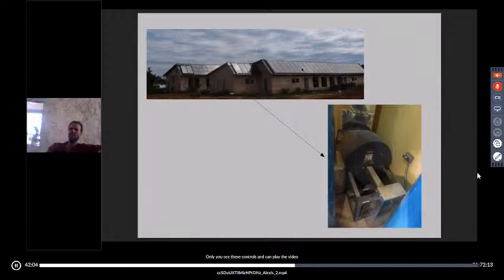A word of caution here: a well-made solar collector, and these are probably not well-made by that criteria, in a dry climate can reach ignition temperature. You don't want a wooden frame around your solar collectors. This is what happened back in the 70s or 80s, somewhere back there. A company in California made redwood-framed solar hot water collectors and realized years later that under particular dry conditions, when no fluid was being pumped through the collectors, they could actually set themselves on fire.